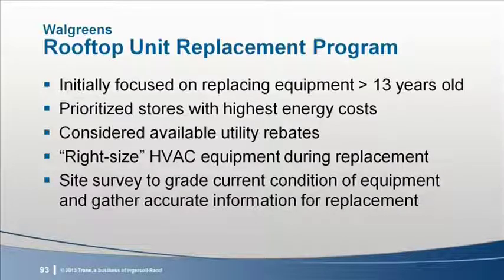Okay. So currently I understand you're using units with 2-speed fan control. Are you looking at the variable speed, the SingleZone VAV kind of concept? Have you been considering that at all too? In 2010, to Akeem's point, the focus was, as you said, starting somewhere. Before that, Walgreens' focus was really making sure that they were expanding their footprint. In 2010, they got to a point of saying, okay, we've got 7,500, 7,600 sites across the country, including Puerto Rico. It's probably a good idea for us to look back and invest some money back into our existing footprint versus making sure that we're expanding at the rate that we have been. So 2010 was that 13-year-old benchmark that Walgreens looked at and said, stores or equipment older than that, let's make sure we look at those first.